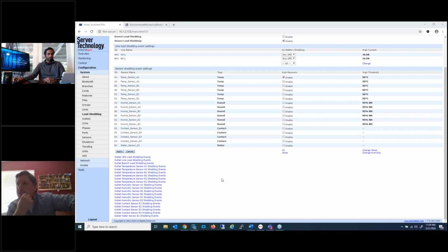All right, another question. Could this also be used as a rudimentary method for power cycling life testing? Looks like it could be triggered via temp. Yes, definitely. Whatever purpose you have, if switching an outlet on and off achieves your goal, we can set that up for all of these different events: humidity, temperature, the UPS event that we started with, and then the current through either the lines measured at the input or through each circuit breaker, as well as the contact closures and water sensors. There are a number of different possibilities out there.